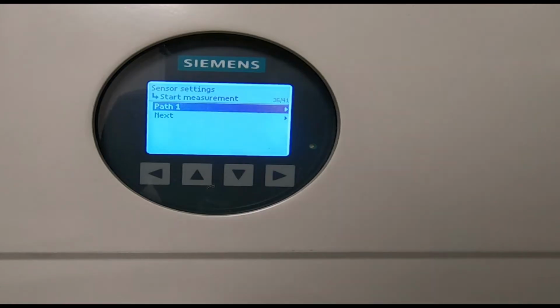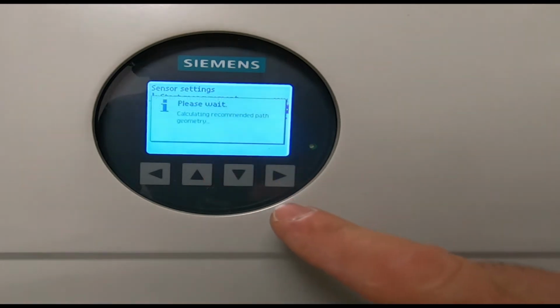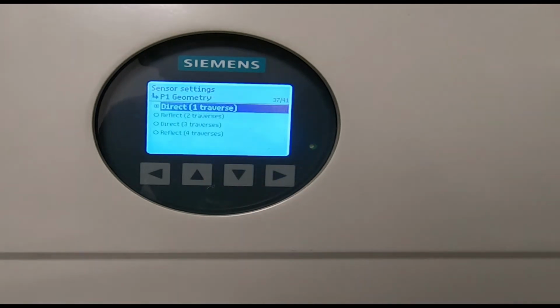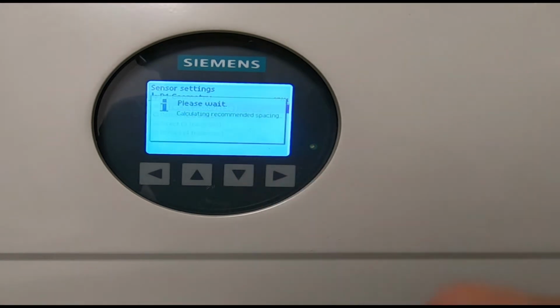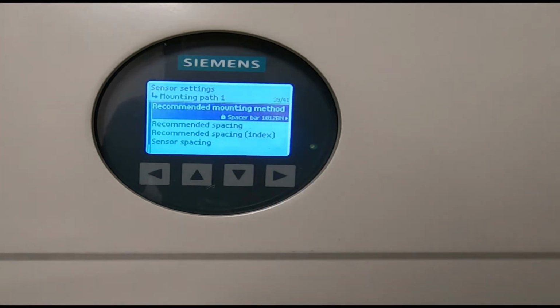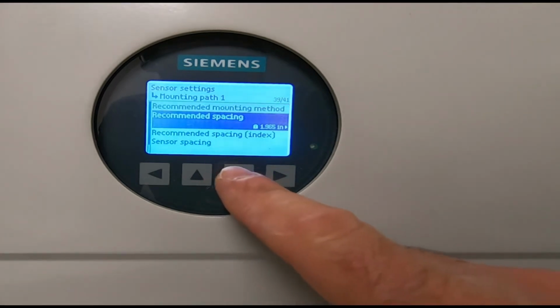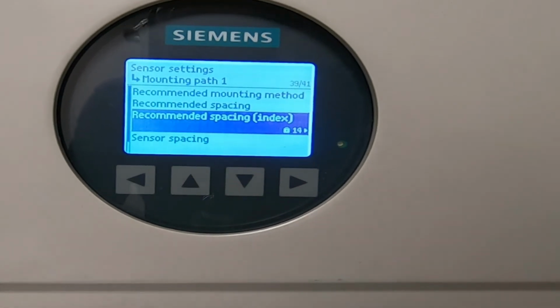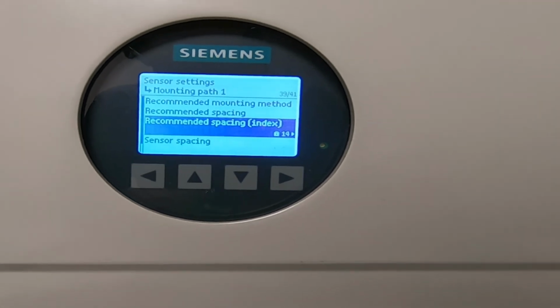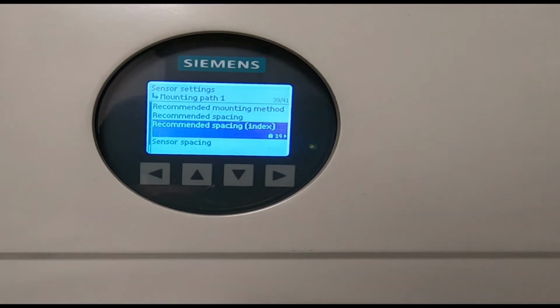Here's the pipe on which we'll be installing our flow sensors in direct mount. As always, start by programming your flow meter for the proper pipe size and sensor selection. Then proceed to the Start Measurement section of the menu, where you'll get your transducer spacing. The meter indicates direct mounting, so we go forward, and now we can get our spacing, and it tells us that our spacing index will be 14 for this pipe. So that's all we need to know. We can now go to the pipe and install our mounting frames and flow sensors.